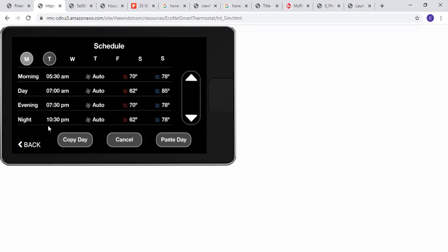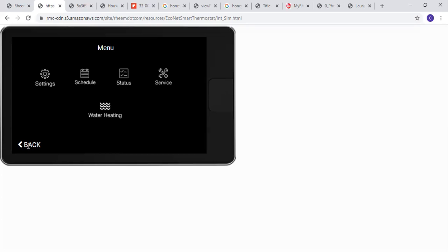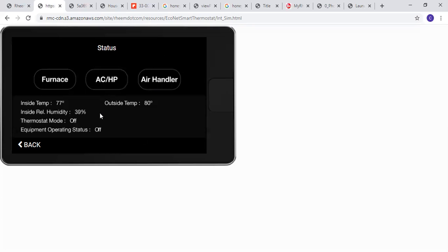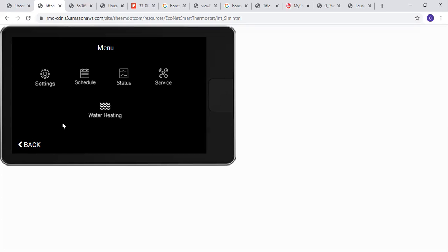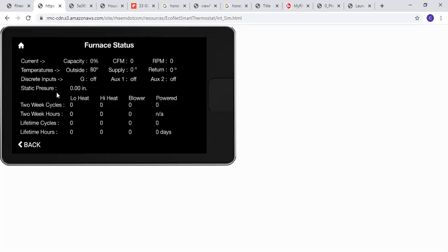Schedule is easy enough to do. You can do it here or on the app. Now this is one I really like here, your furnace status, because I'll keep talking about static pressure. So you have the furnace running, or let's say air conditioner's running. You can go over here to the furnace and check right here. Obviously, air conditioning is your highest RPMs, so you can actually look right here and see what your static pressure is. And this is actually pretty accurate. If I individually test it against this, it's only going to be a point or two off.